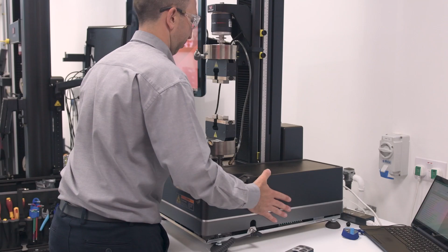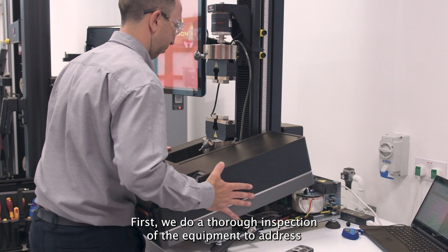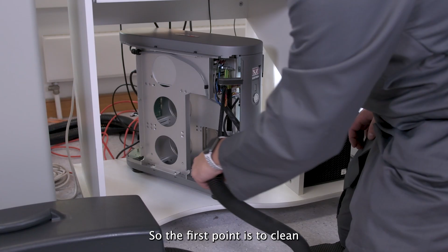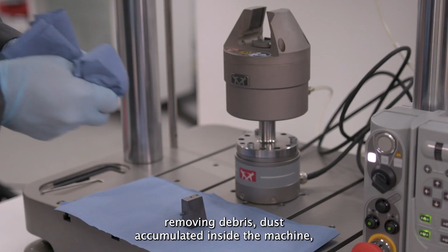So what does normal preventative maintenance look like for your testing equipment in the laboratory? First, we do a thorough inspection of the equipment to address any issues due to wear or damage. The first point is to clean, removing debris and dust accumulated inside the machine, and checking all connections, electrical and mechanical.